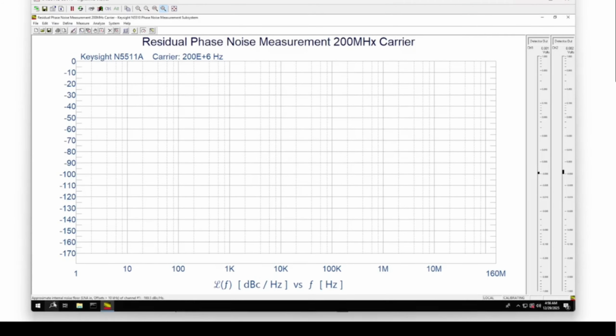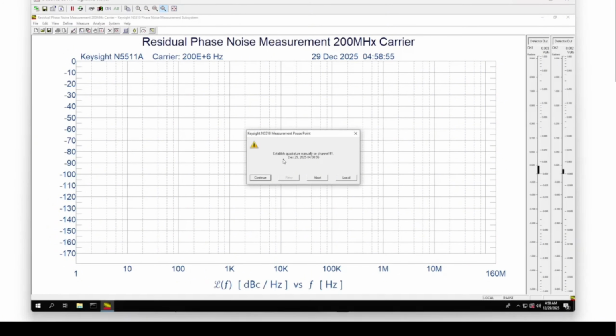So you can see what's happening at the bottom of the screen. It's telling me it's calibrating and it's applying a few things. So now it says remove modulation from carrier signal and connect the DUT. So we'll turn off PSG2 RF power. And now connect the DUT if you have one. I'm just gonna connect it across. So now I'm done. I'll hit continue. And now it'll ask me to establish quadrature manually on channel 1. Why is that? If you notice, we're reading about 0.003 volts. We ideally want this to be as close to 0 as possible. If you could hit LS001, it should then stop complaining.